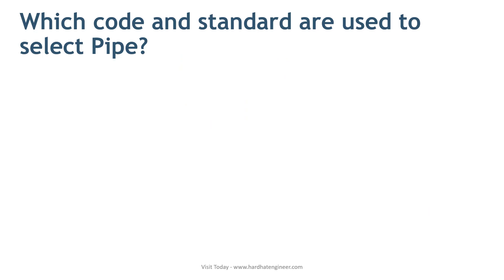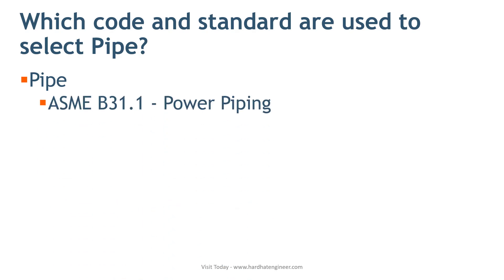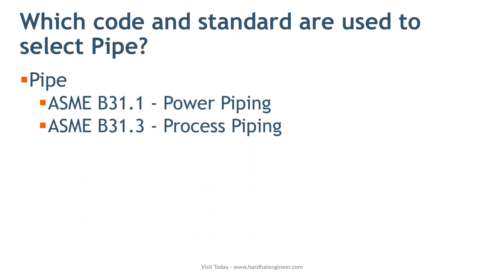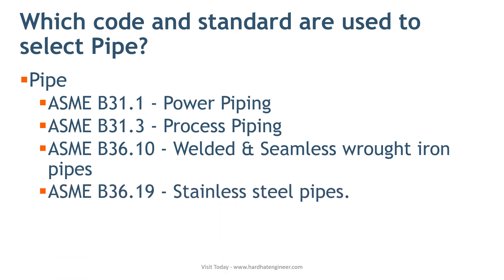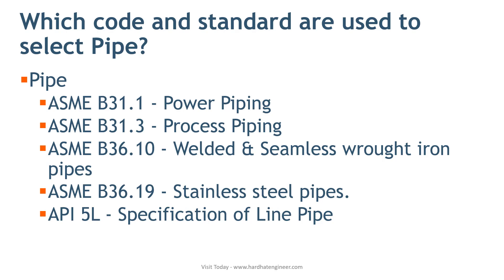Which codes and standards are used to select pipe? Different standards are used for different piping components. Selection of pipe material is done based on the piping design code such as ASME B31.1 for power piping and ASME B31.3 for process piping. Dimensions of carbon steel and stainless steel pipes are given in ASME B36.10, which covers welded and seamless wrought iron pipe, and ASME B36.19, which covers stainless steel pipes. API 5L pipe specification is also used in the petroleum industry for dimensions of carbon steel pipe.